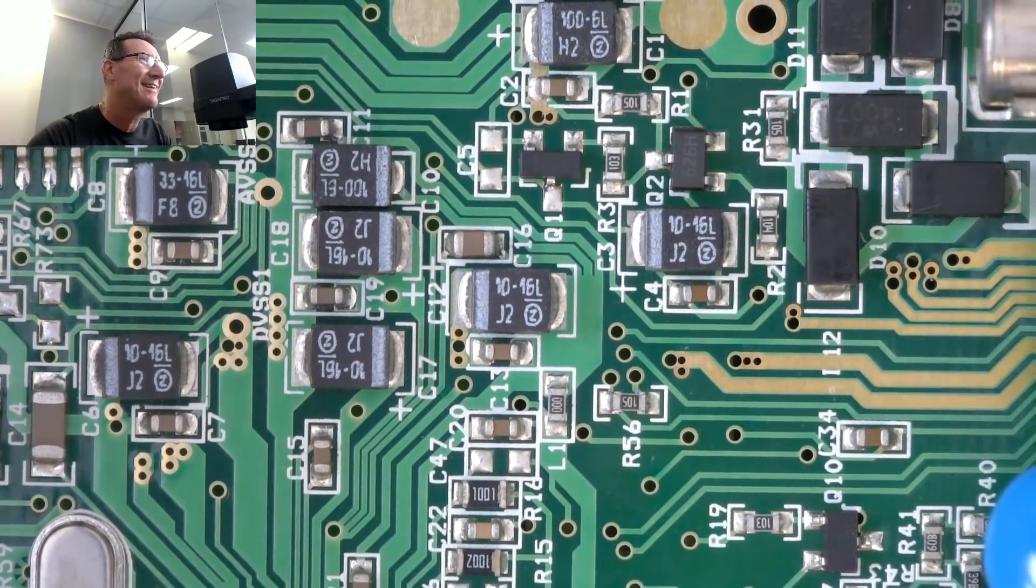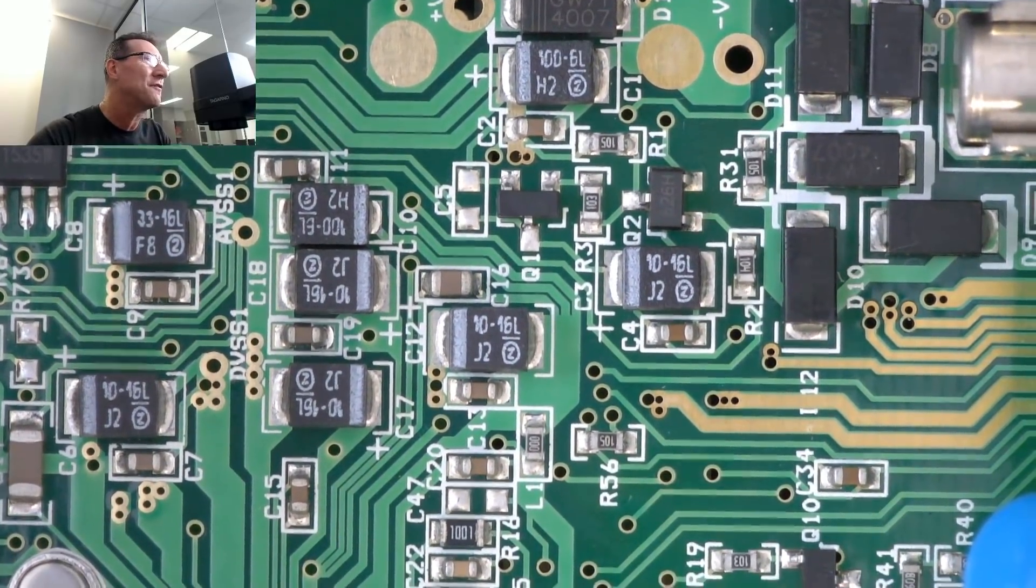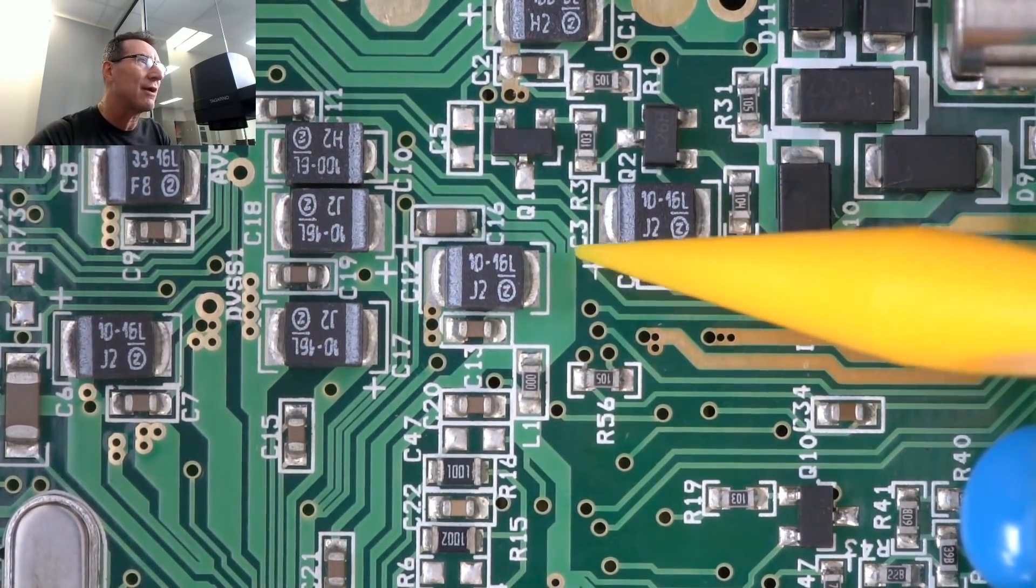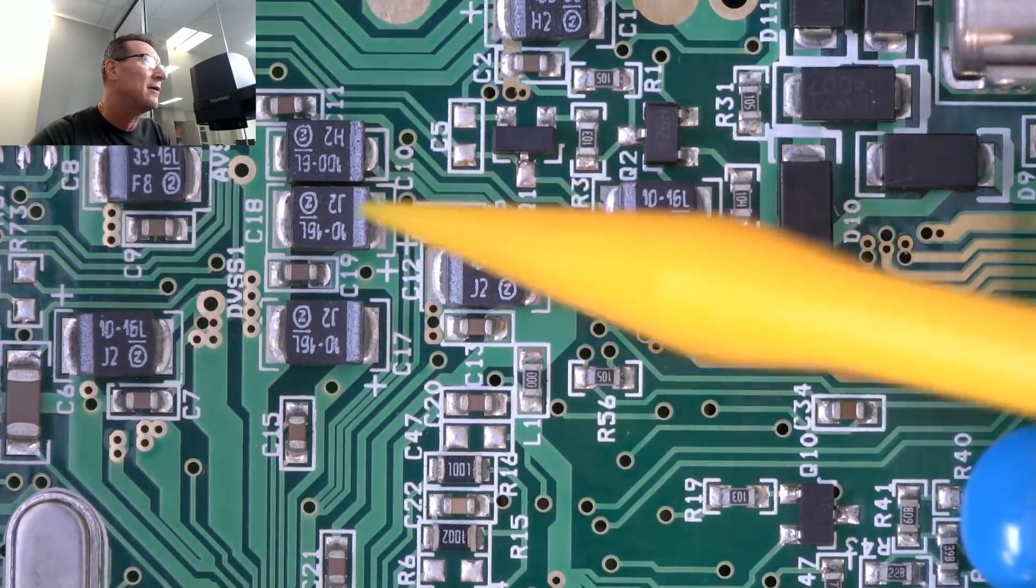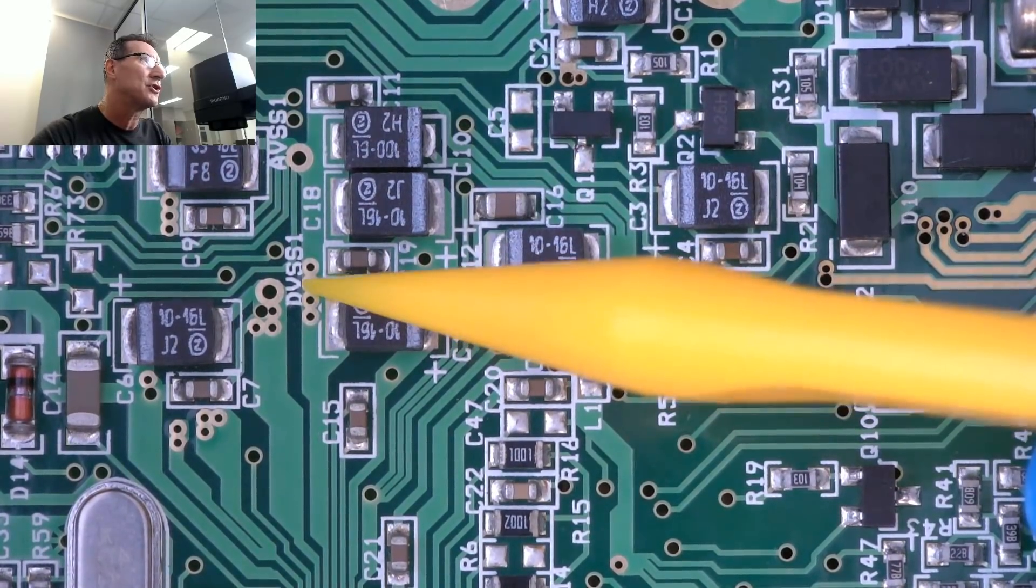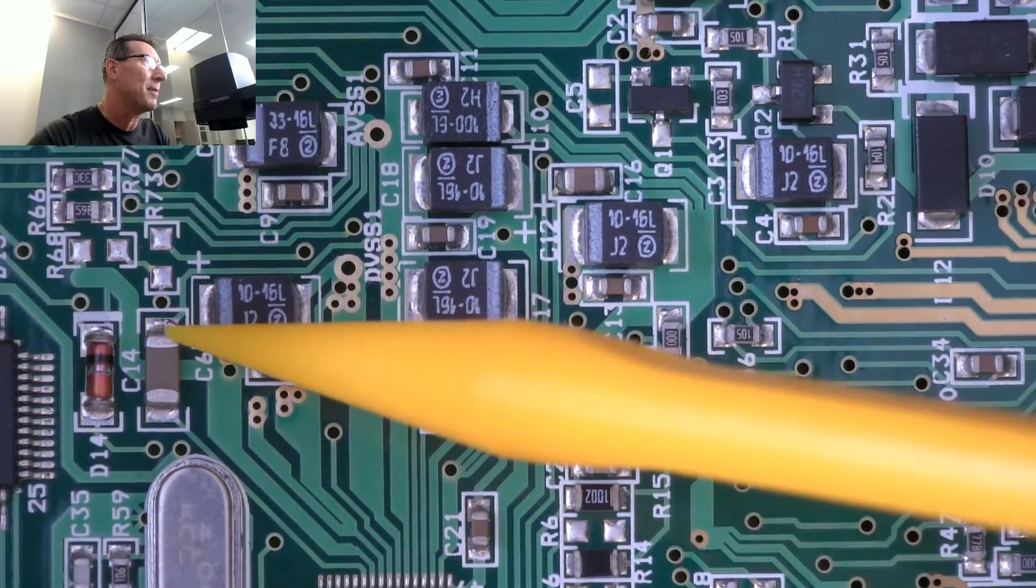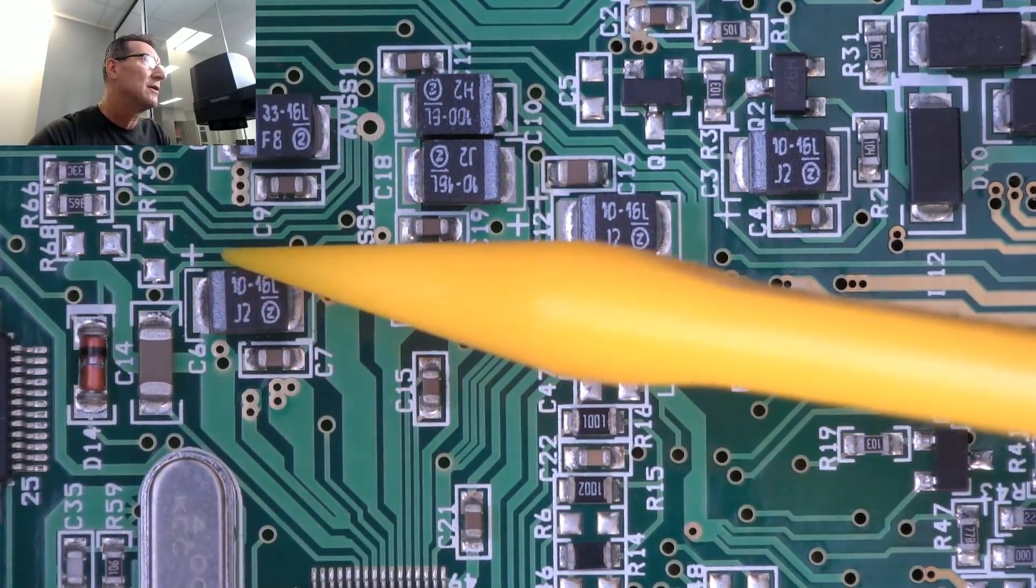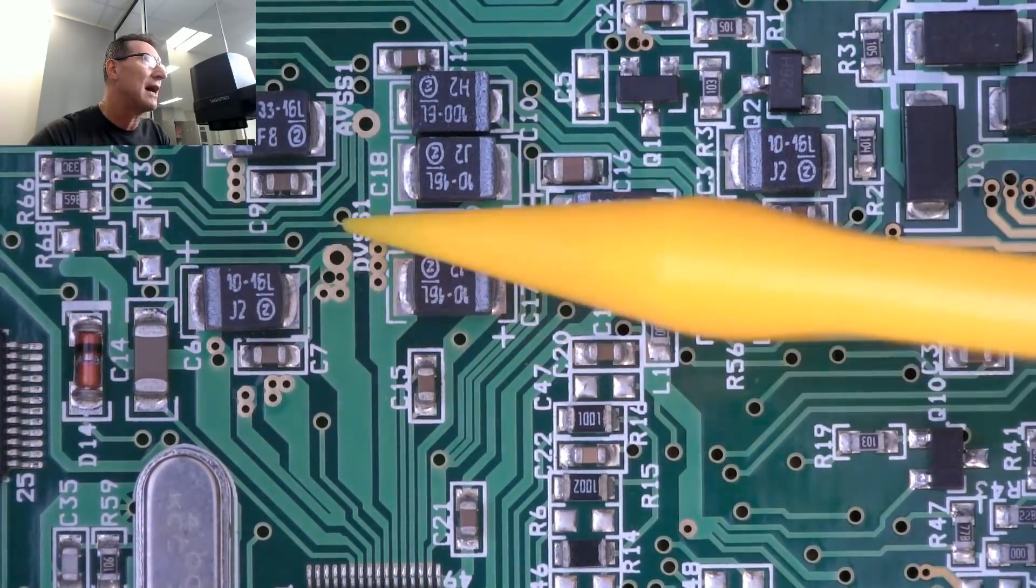So, once again, I'm going to have to give this a good thorough going over under the Mantis. And see, these are all your range resistors and other stuff in here, because these are all your input range switching and stuff like that. So, if you're going to suspect some sort of component or solder joint or something like that, there's a decent candidate area to do that. You always suspect tantalums. I mean, if I get desperate, you would start ripping out tantalums. But once again, I don't know how this could affect the cause, the issues that we're seeing here.